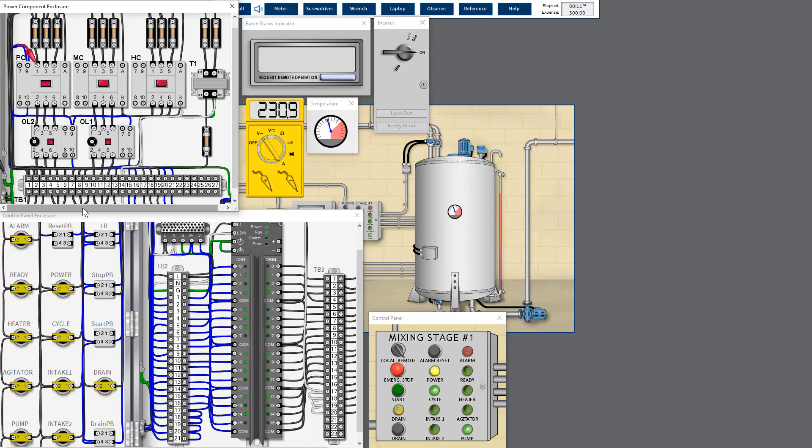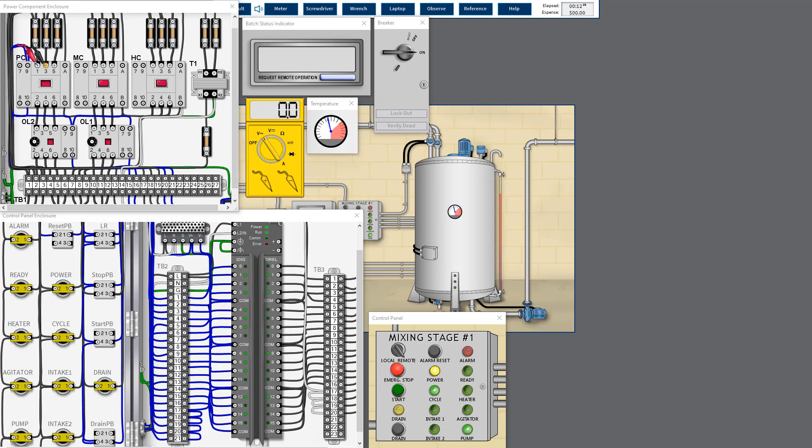In summary, for three-phase circuit, as a rule of thumb we can measure the phase voltage if the line end is open, but we have to measure line to line voltage otherwise, meaning if there is no line end open. Understand, for this case the line end is not open because the pump contactor button is actually push inside automatically. Push inside automatically meaning the contactor coil was energized and the three-phase contactor switch is triggered from normally open to close. So the current can flow through freely towards this three-phase circuit, so we have to measure line to line voltage.